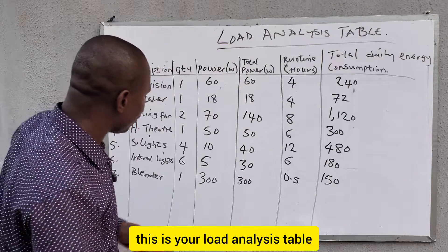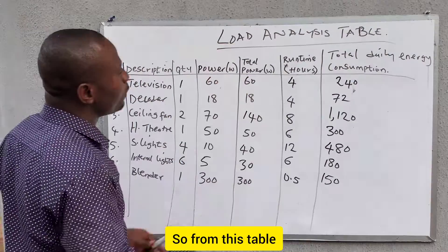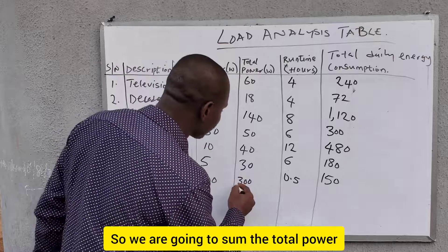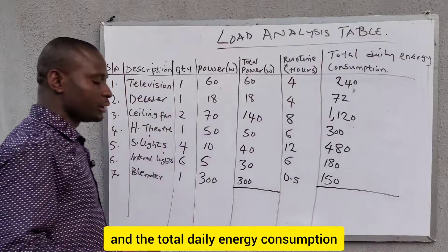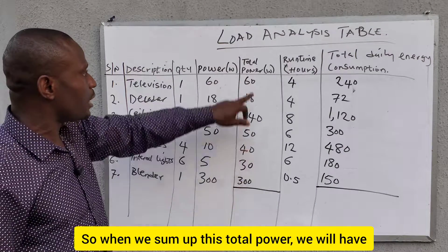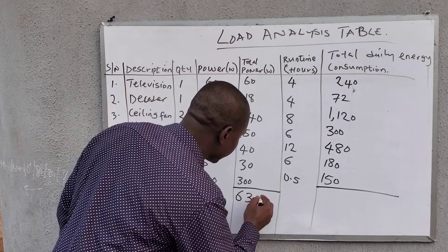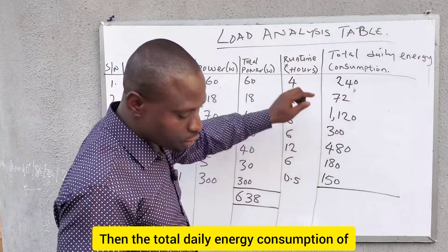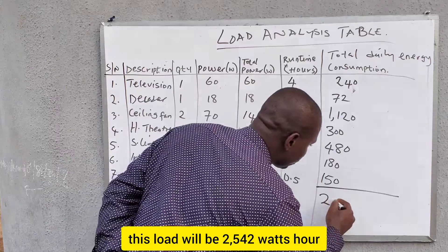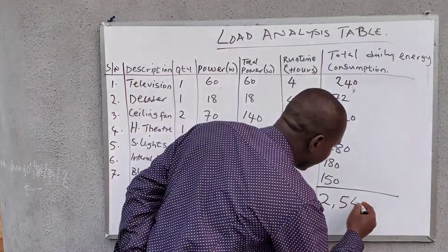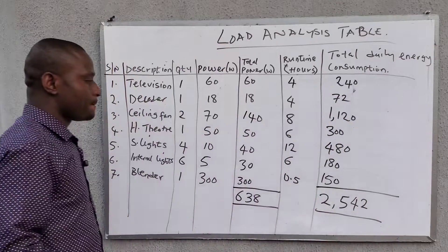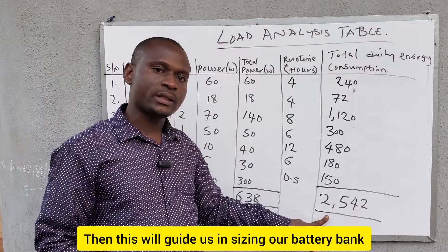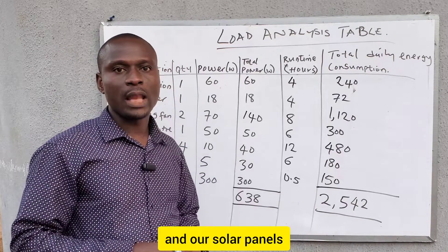Now you have your completed load analysis table. The columns we concentrate on are total power and total daily energy consumption. When we sum up the total power of all loads, we get 638 watts. The total daily energy consumption of all loads comes to 2,542 watt-hours. We will use this information to size the inverter, and it will also guide us in sizing the battery bank and solar panels.